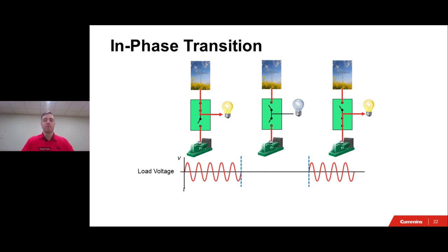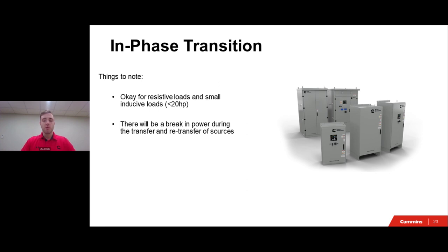That means there is no more power to your loads. And then on the third part on the far right of the diagram, the automatic transfer switch has closed on to the emergency power supply. And then now you have power once again being restored to your loads. The break, like I said, the break in power is now over, and you once again have power to your loads. So that retransfer will look pretty similar once the automatic transfer switch has sensed that your normal supply is good to go. It will open up to your emergency power supply, being that generator. There will be a brief interruption of power, and then it will close back on to your normal source, being the utility. So this type of transition will work for most applications. However, it is not suitable for applications with large motor loads. Also, please keep in mind that on these types of transitions, on both the transferring of power and the retransferring of power, there will be a brief interruption to your loads as the automatic transfer switch opens and closes onto the normal and emergency power sources.